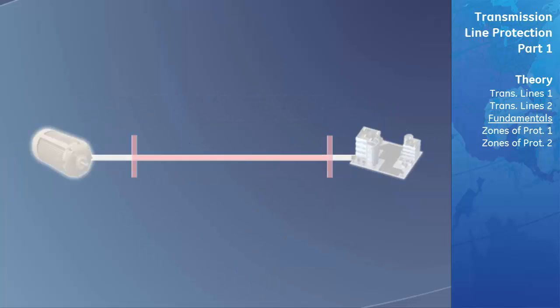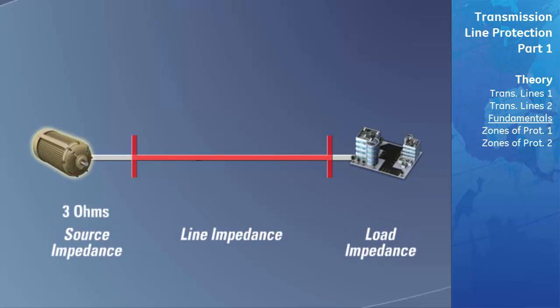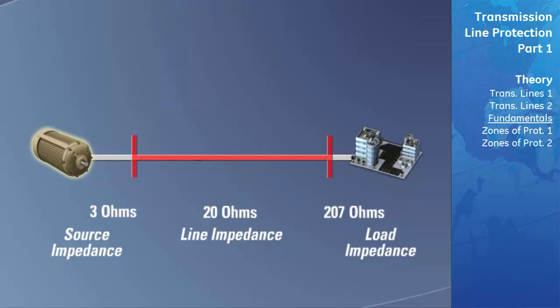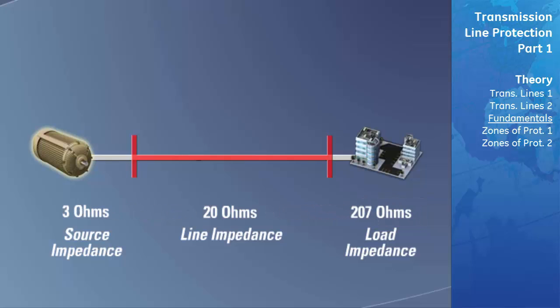Each component in a power system, whether it is a source, a transmission line, or a load, has an impedance. This total system impedance limits the magnitude of current that will flow through the power system. In the power system seen here, we have a total system impedance of 230 ohms. If the source were generating power at 230 kilovolts phase to neutral, 1000 amps of current would be supplied to our load.